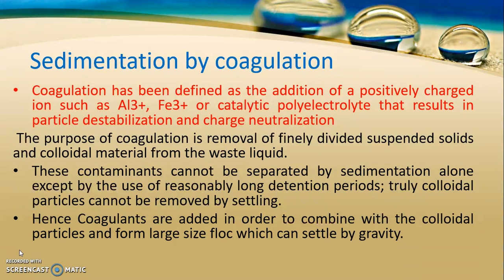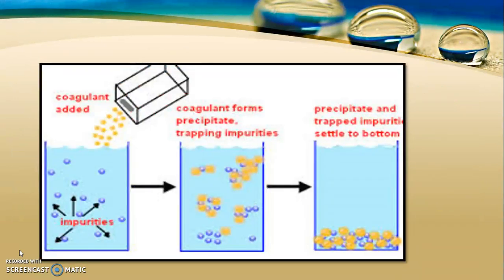The purpose of coagulation is the removal of finely divided suspended solids and colloidal material from the waste liquid. These contaminants cannot be separated by sedimentation alone except by using very long detention periods, which is not feasible. Therefore, these particles have to be removed by adding coagulants. This picture shows the impurities in suspended motion in water; when coagulants are added, they combine, increase in size, and settle down by gravity.